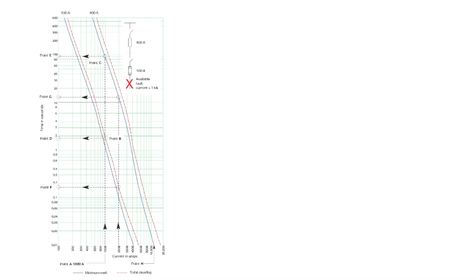Time current characteristic curves, or simply time current curves, are graphical representations of fuse operation under different overcurrent conditions as plotted by amps and time. These curves also provide a visual means for comparing overcurrent protective devices against one another for purposes of selective coordination analysis.